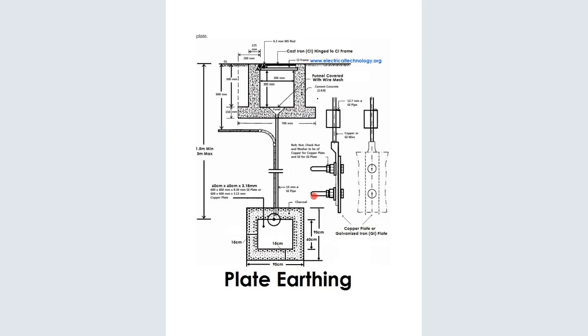So you can see now that is the plate earthing. As we had talked about it, now these are the, I think this is the cast iron frame. You can see the copper plate, the galvanized iron there. So the 60 by 60 by 3.3 plate is here. You can see how it looks like. So all this is the apparatus that is supposed to be earthed, and all the cables are being connected down to the plate so that it can increase the surface area of dissipation of the excess charges in the ground.